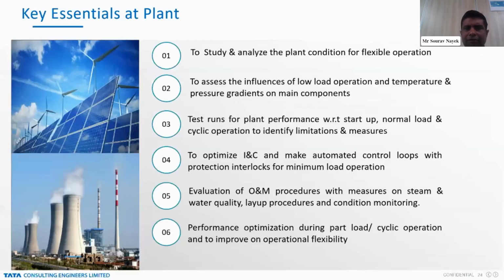What are the key essential steps we should take for flexible operation? First, we should study and analyze the plant condition for flexible operation, whether there is any limitation, and identify any bottlenecks in the plant. Then we should assess the influence of low load operation and how the temperature and pressure gradients will impact the main components, in the boiler, in the turbine, in the pressure parts, in the turbine components. How the different temperature and pressure gradients during low load operation impact them, we need to evaluate.